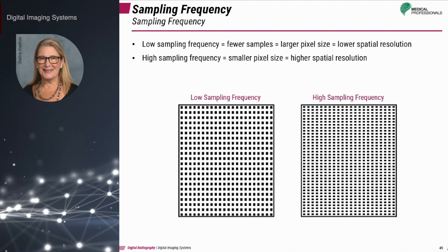Sample frequency is the number of pixels sampled per millimeter and controls spatial resolution in CR. More pixels sampled means increased spatial resolution. However, sample frequency can change from vendor to vendor, varying from 5 to 20 pixels per millimeter. The choice of sample frequency is based on plate size. Low sample frequency means fewer samples, larger pixel size, and lower spatial resolution. High sample frequency gives smaller pixel sizes, more of them, and higher spatial resolution.